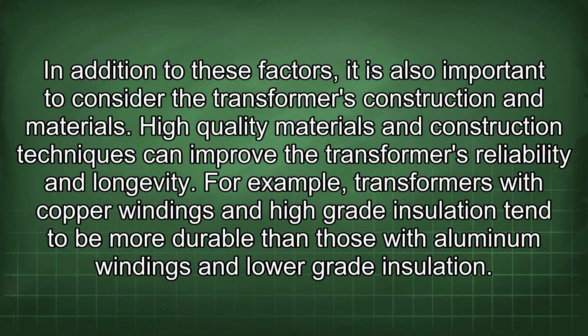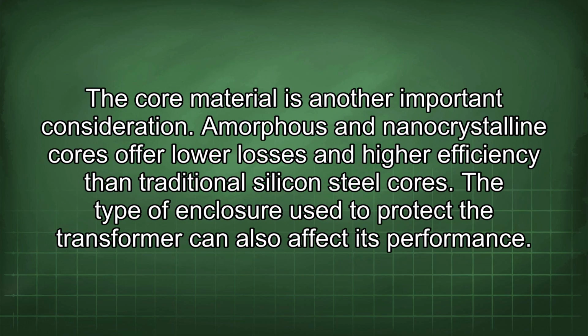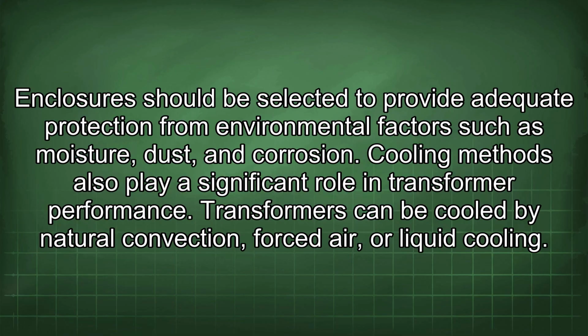In addition to these factors, it is also important to consider the transformer's construction and materials. High-quality materials and construction techniques can improve the transformer's reliability and longevity. For example, transformers with copper windings and high-grade insulation tend to be more durable than those with aluminum windings and low-grade insulation. The core material is another important consideration. Amorphous and nanocrystalline cores offer lower losses and higher efficiency than traditional silicon steel cores. The type of enclosure used to protect the transformer can also affect its performance. Enclosures should be selected to provide adequate protection from environmental factors such as moisture, dust, and corrosion.